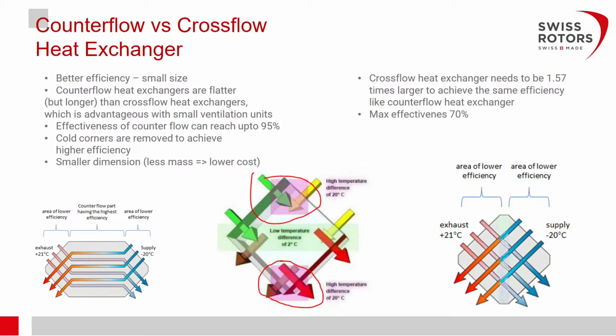Some differences between the counterflow cross-plate heat exchanger and the cross-plate heat exchanger. So on the left side, in the bottom, you see the counterflow plate heat exchanger, and we are showing this middle part, which is where we have this counterflow pass of the two streams. On the right side, in the normal cross plate heat exchanger, there is no such area. And what are the effects? Of course, in the middle part, there is the highest efficiency. And in these small triangles at the entry on the left side and on the right side, there is much smaller efficiency. So normally it works like the cross plate heat exchangers.